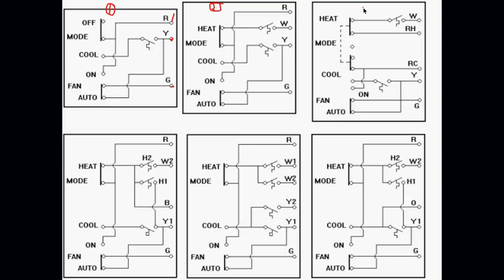What about number three? What have we added? I have an extra R terminal, don't I? RH and RC. I now have an RC and an RH. All this says is I can use two separate transformers. RC is on my cooling system, RH is on my heating system. This setup has been used in oil systems. So this setup is very specifically for oil, because your oil system has its own transformer right built as a part of the primary control. You have an RC, which is for your cooling side.